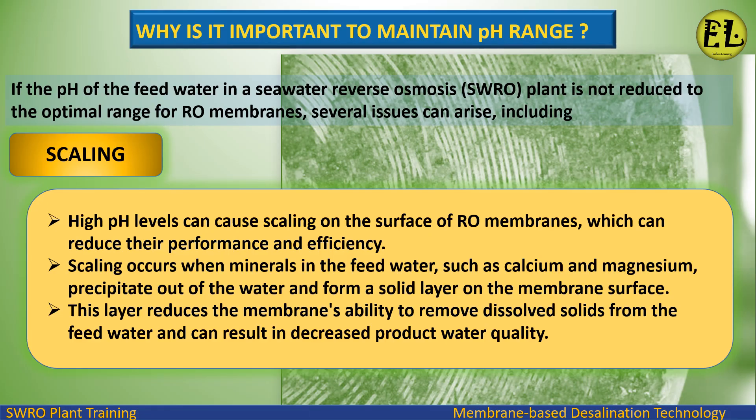Why is it important to maintain pH range? If the pH of the feed water in a seawater reverse osmosis plant is not reduced to the optimal range for RO membranes, several issues can arise, including scaling. High pH levels can cause scaling on the surface of RO membranes, which can reduce their performance and efficiency.